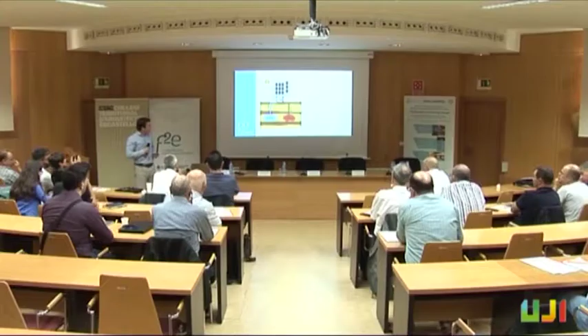when we use ATES, when we use storage. During summer we are cooling the building with the groundwater. But while we are cooling the building, at the same time we're actually storing heat in the warm well. And during winter we're going to reuse that heat again for heating purposes. And while we are heating the building, we are again storing cooling capacity.